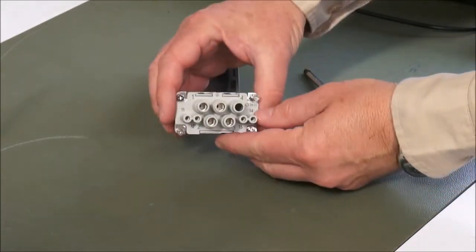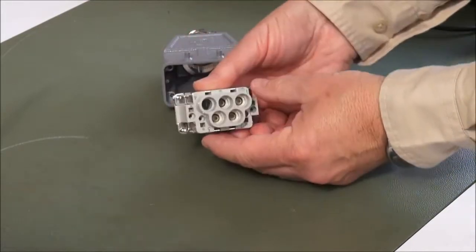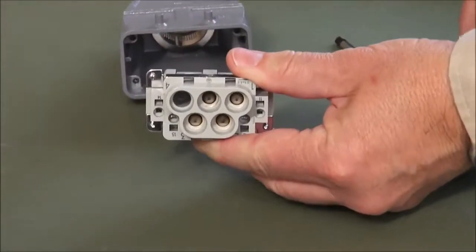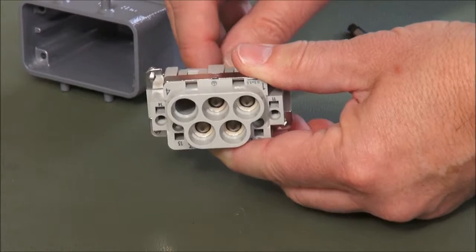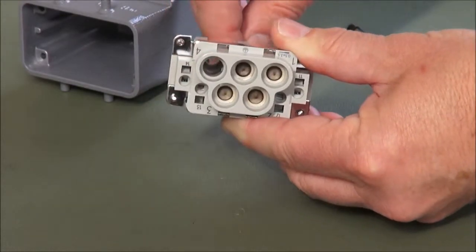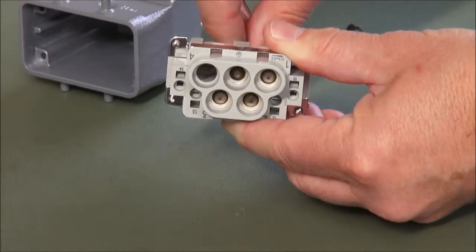And the critical thing on the back of the Harting connector where the cables go in are these conical clamps. And these conical clamps are operated so that you retract the conical clamp like this and then you would put in the appropriate cable around the clamp.